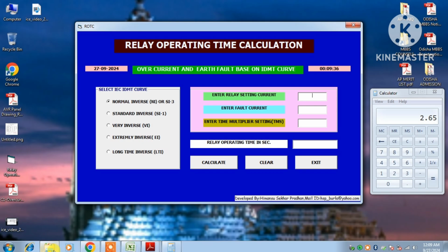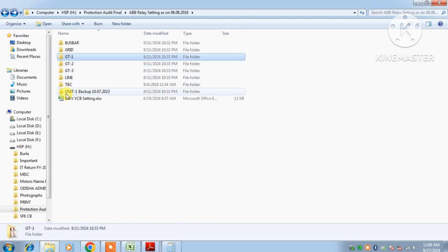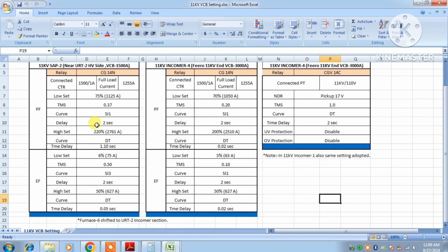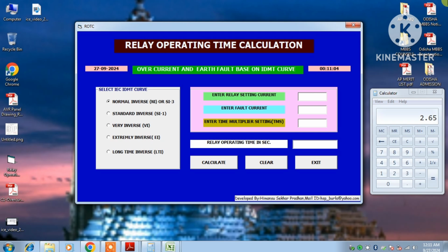One more setting file I will show you. This is the 11 kV side settings. In this case, the relay we are utilizing is the CG 14N, and the full load current is 1500 amps, and the setting current is 75% of that, which is 1125 amps. TMS is given as 0.37, and the curve given is SI1. So 0.37 is the TMS, SI1 is the curve, and the setting current is 1125 amps. If you fill these parameters in, 1125 is the setting current.